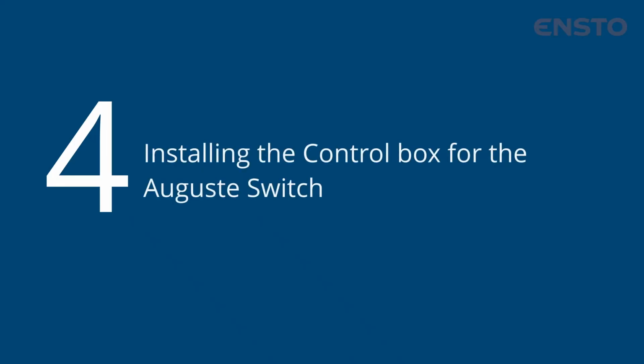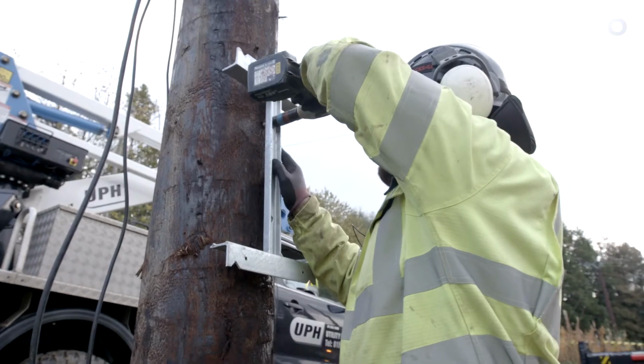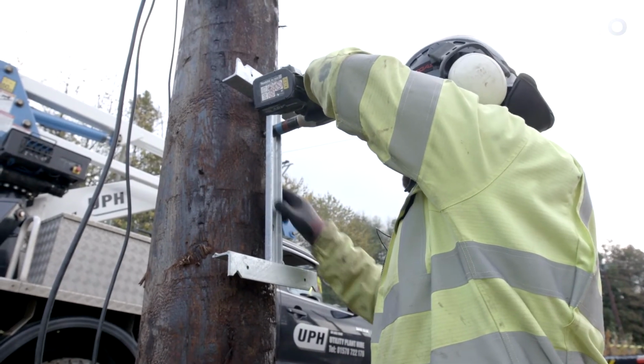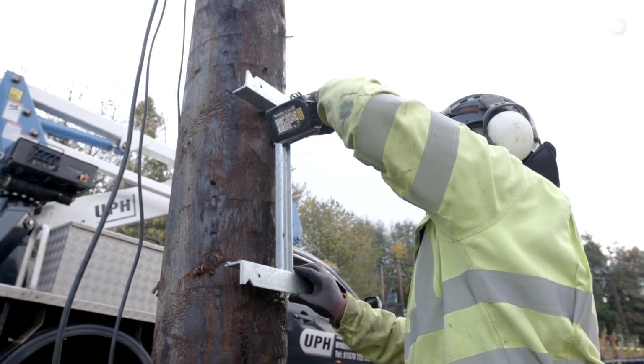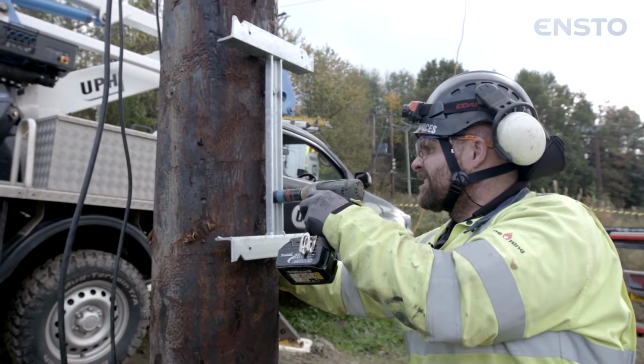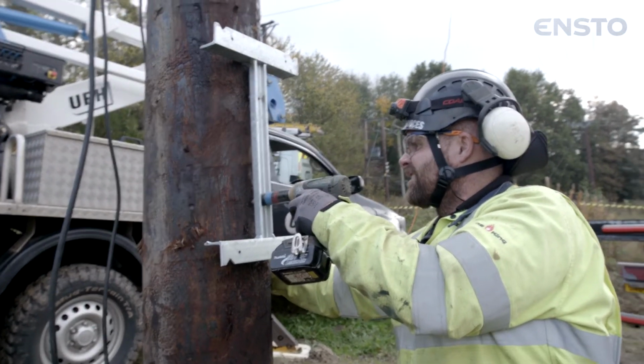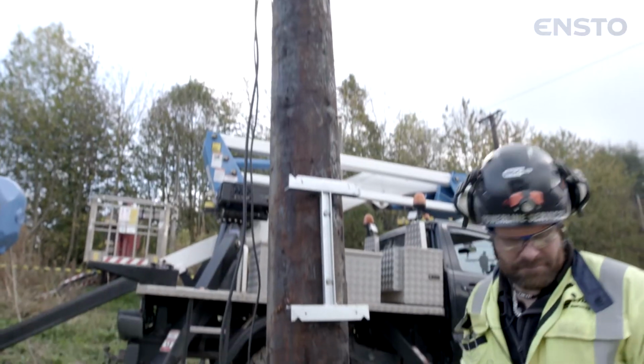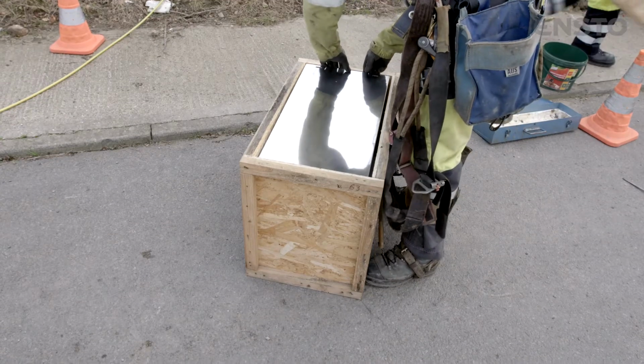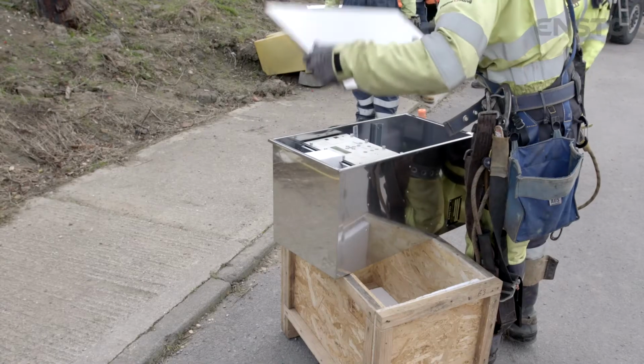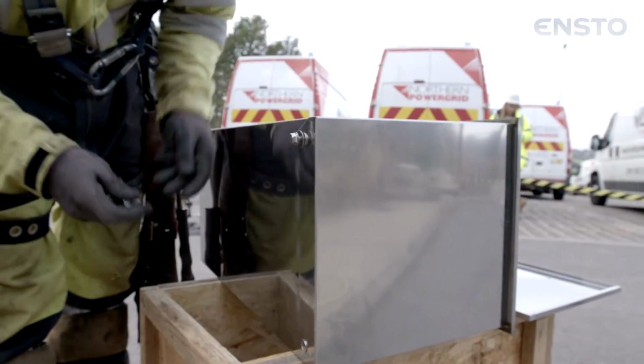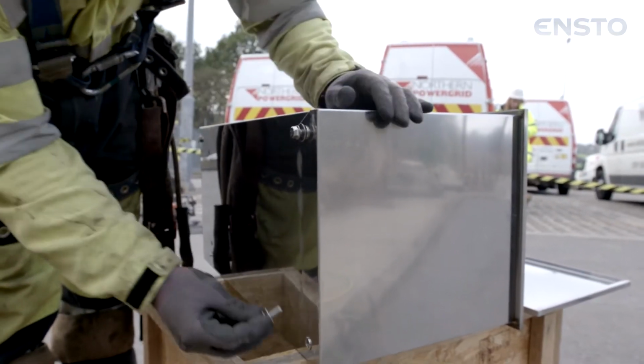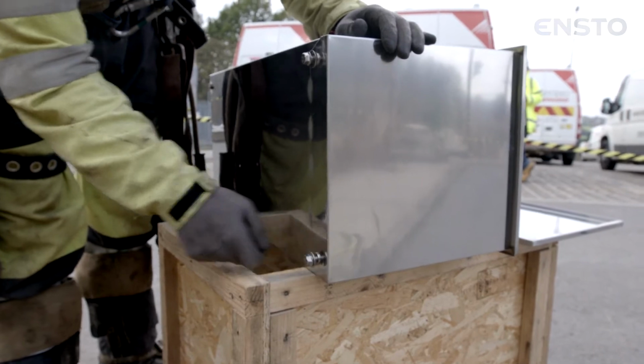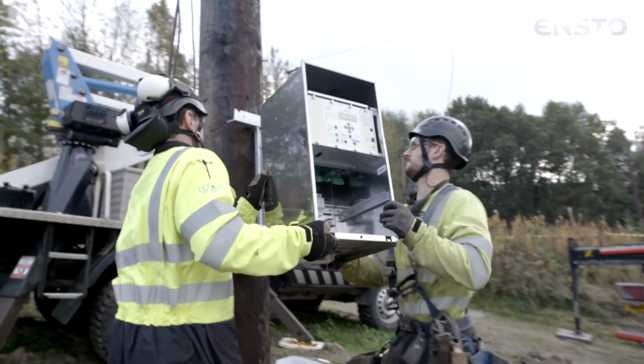Stage 4. Control box. Mount the control box bracket on the pole at the height specified by the network operator. Often, this will be approximately 2.5 meters from ground level, above an anti-climbing guard. 2 coach screws will hold the bracket onto the pole. Then, install 2 screws into the top rear of the control box. These locate onto the bracket on the pole when mounted.